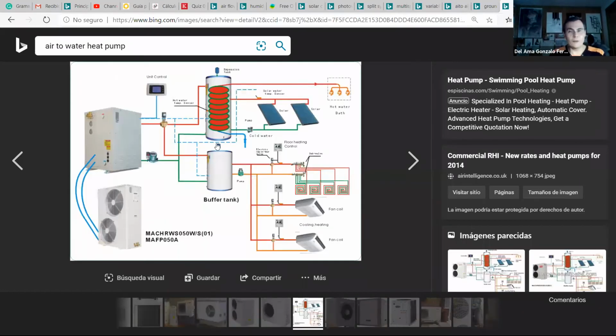So do we have a mechanical room? No, we don't. Okay, so without a mechanical room, we cannot place water-to-water. So you have to make that decision immediately, and then keep on designing. But making the decision, there is not one right decision. I cannot use water-to-water heat pumps always. It doesn't work like this because it depends on a lot of things. Water-to-water heat pumps are much more expensive than air-to-air heat pumps.